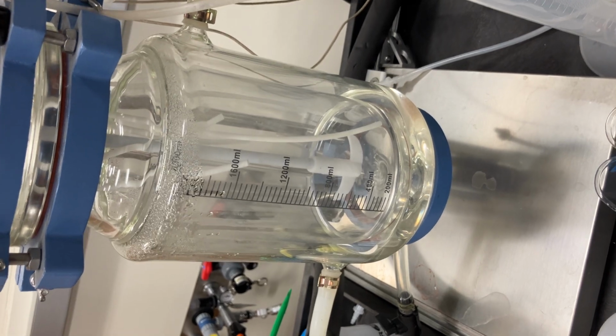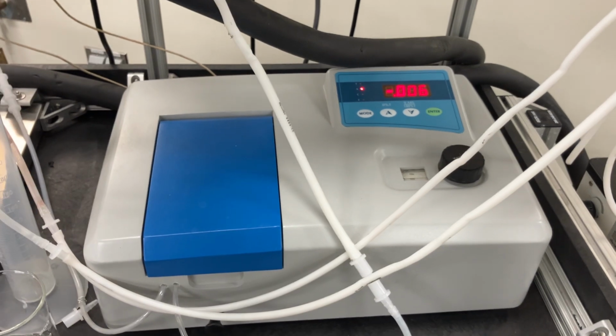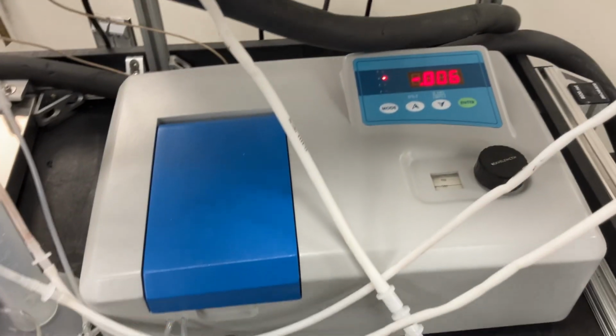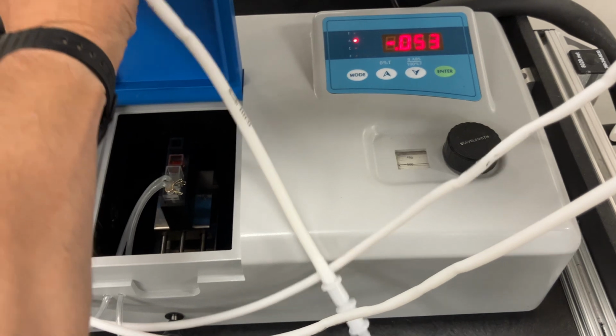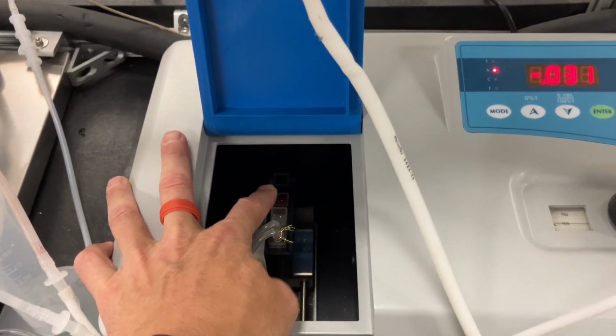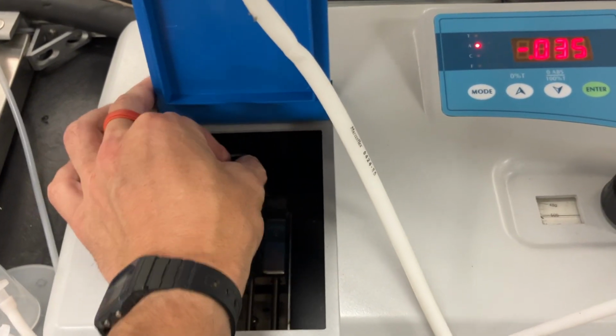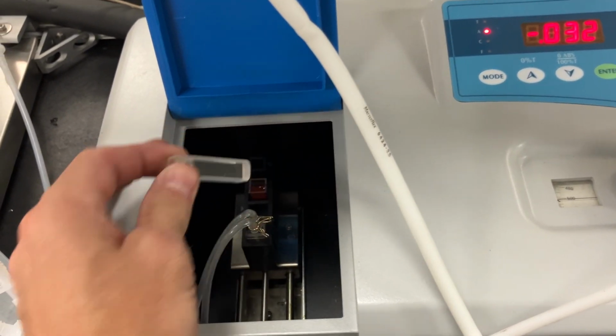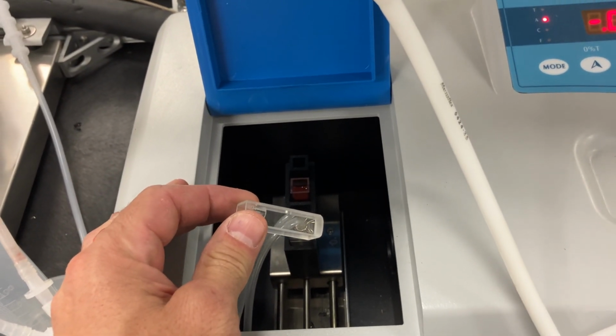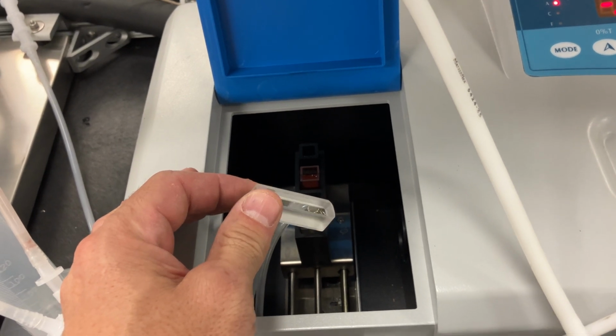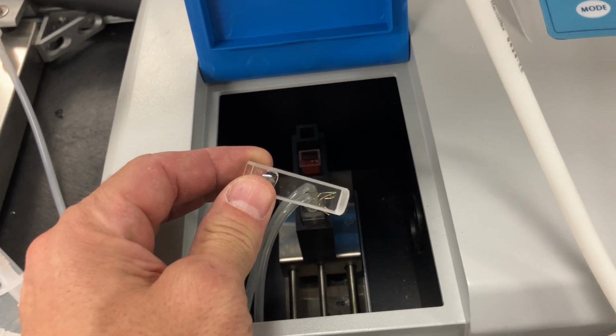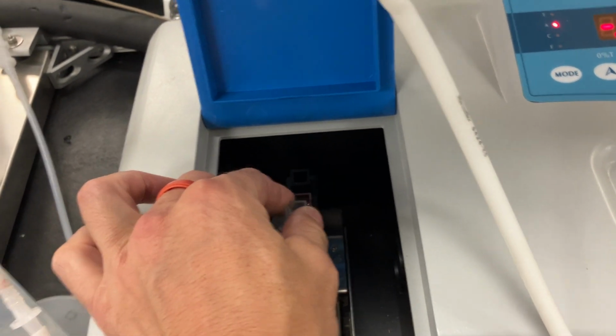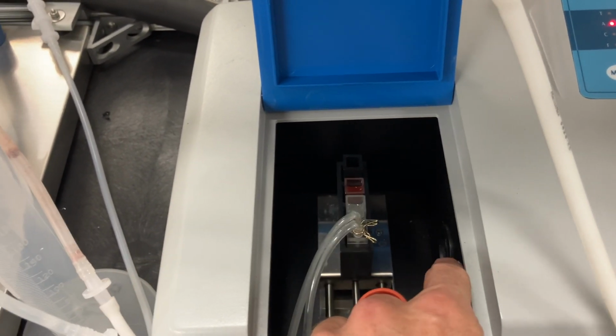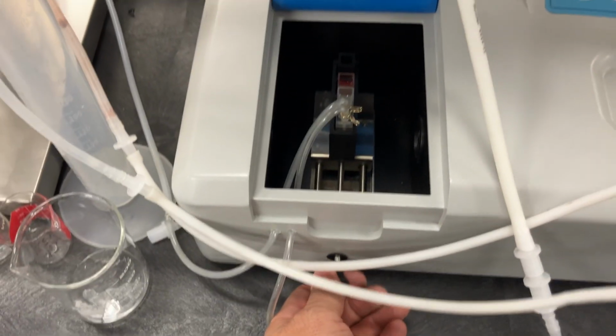And on the out, you can head over to the spectrophotometer to measure the absorbance. To zero this, you're going to use a black cuvette that's here in the back and one that's filled with distilled water or another liquid of your choice. Notice there's a frosted side and a clear side. Make sure the clear side is in the path of the light, and you can index it here, so I can index it all the way back to the black.